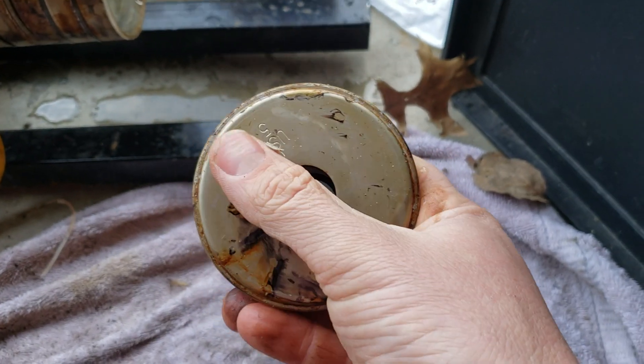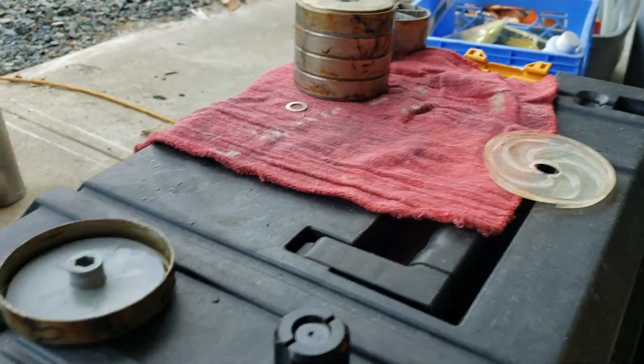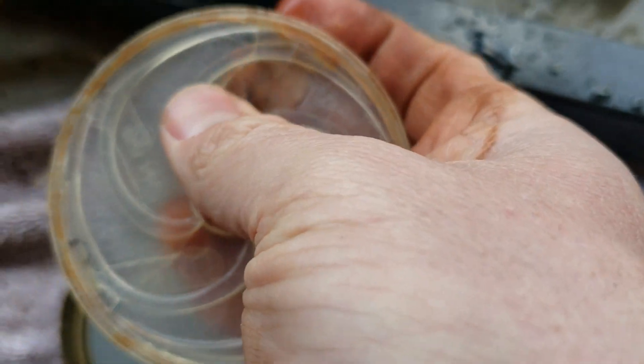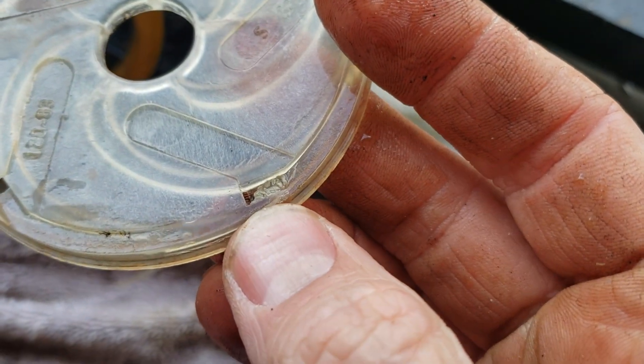These things too — we can set them in some water, take a Brillo sponge or whatever scrubby sponge, just to knock off any other debris. See, as we're taking apart here, Mike's gonna check them out. That one's got a little bit of black on it, and that one too is looking questionable. You can also check the outside edges of these to see if there's any splits, since we're taking them apart. And we've got a little bit more trash right there — see that.